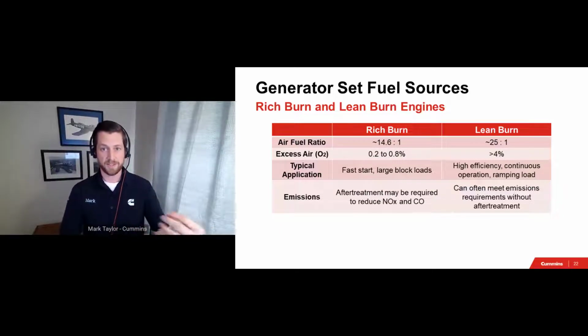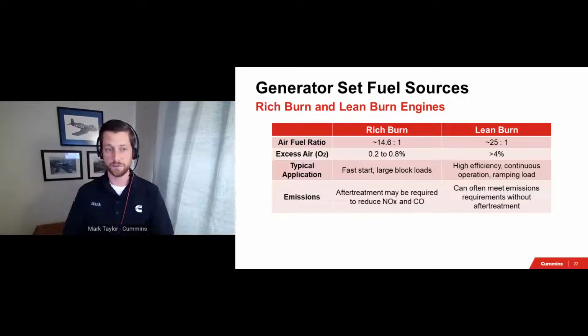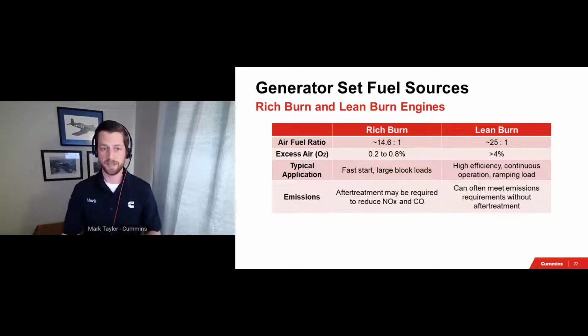The terms rich burn and lean burn generally point to the air-fuel ratios and amounts of excess oxygen in the exhaust. These traits and characteristics are good to know for me as an engineer working for a manufacturer that happens to make engines. But for you as a specifying engineer, what should really matter at the end of the day is the performance of these engines. Investments in engine technology continue to advance, and as such, the lines that divide these two columns in reality are getting more blurred than ever. There are lean burn generator sets that provide rapid response times and load acceptance that make them a valid standby option. There are also peak shaving and continuous applications out there where a rich burn generator set is best suited for the job.